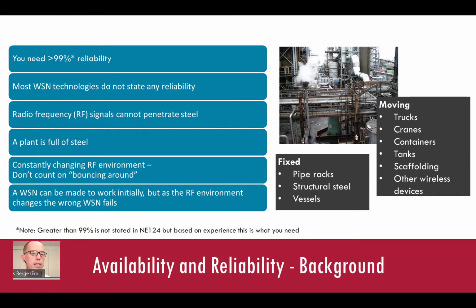This is so because the reliability of most technologies in a plant environment is very much lower than 99%. A plant is a challenging environment for wireless because radio frequency or RF signals cannot penetrate steel. And a plant is full of steel, including metal furnaces and storage tanks the size of multi-story buildings. Moreover, there is a constantly changing RF environment in the plant as heavy vehicles move around and scaffolding goes up, causing radio propagation changes. That is, a wireless sensor network can be made to work initially, but as the RF environment changes over time, with the wrong technology, part of it may suddenly fail.